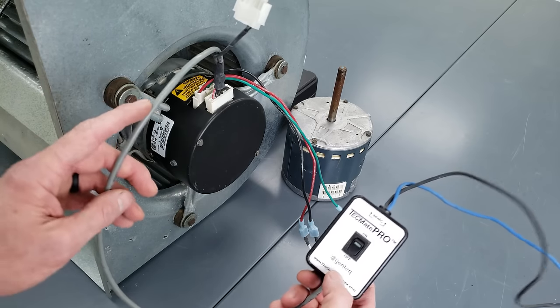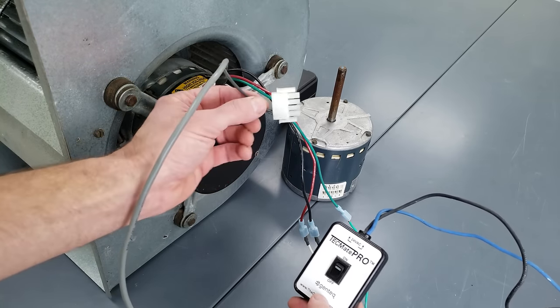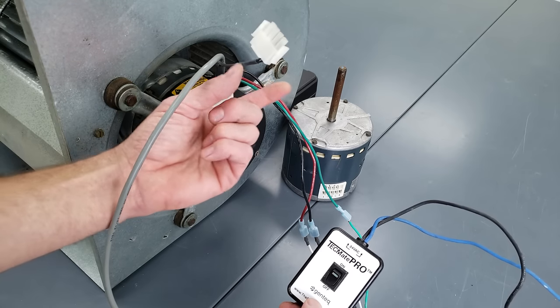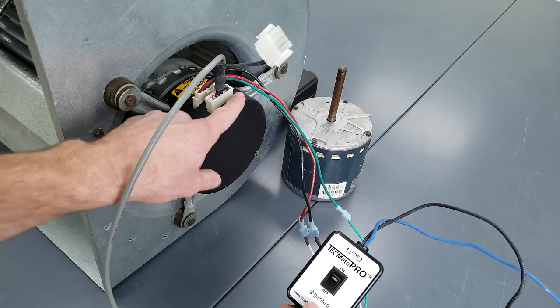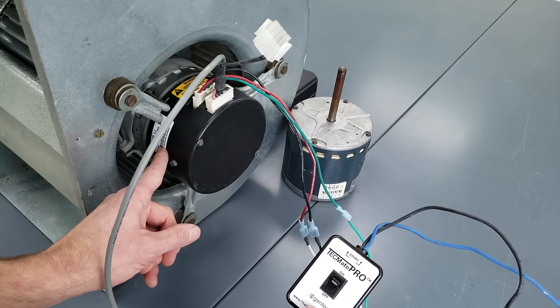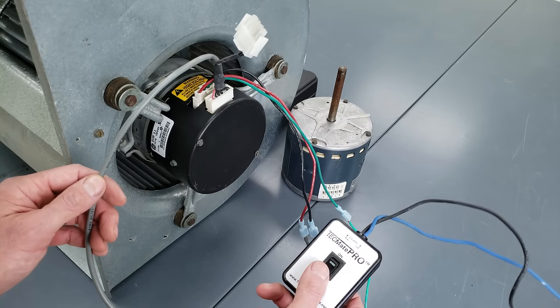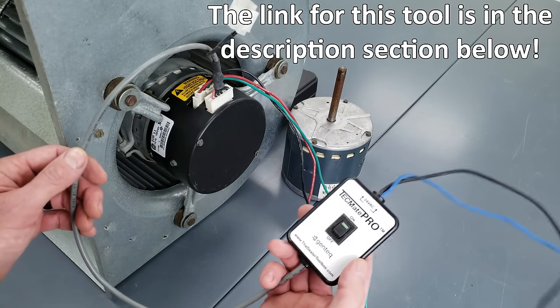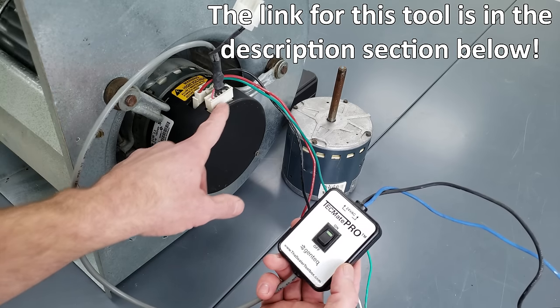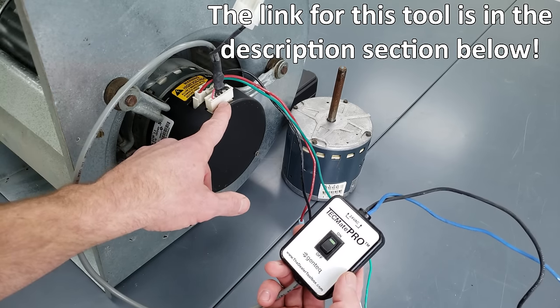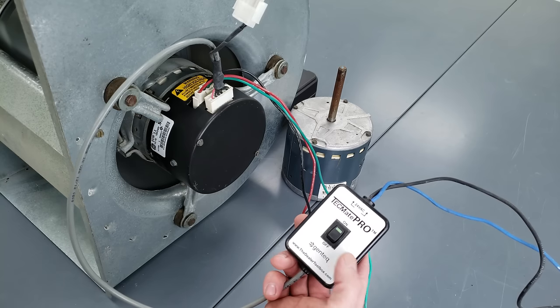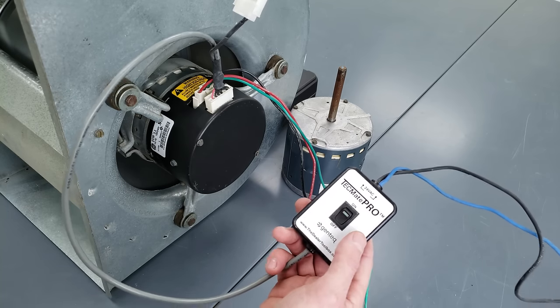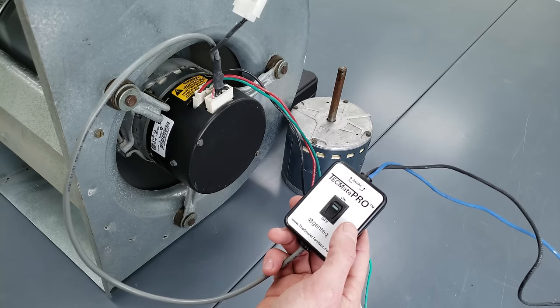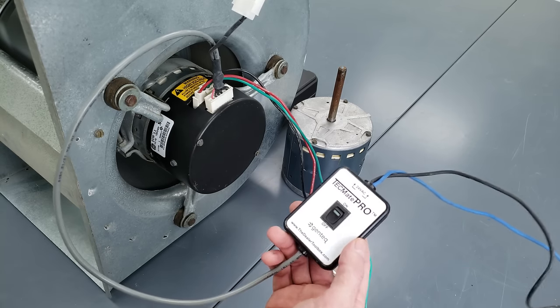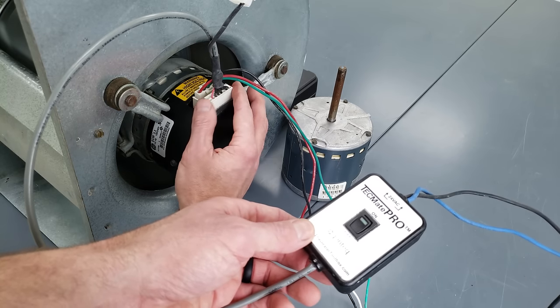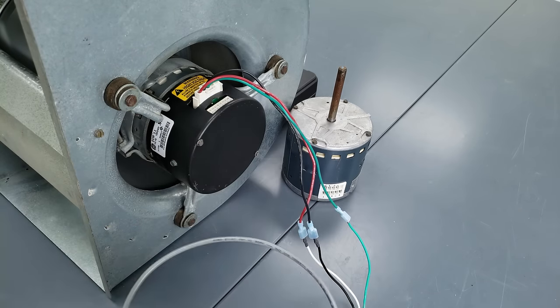This TechMate Pro comes with a 16-pin connector here and a 4-pin connector here, and the 4-pin is for the 3.0 version, and the 16-pin connector is for the 2.3 version. So what I'm going to do is turn this blower motor on by giving it a signal right over here on the 16-pin connector. Now I'm going to tell it to shut off. However, you see that it's not shutting off, and I can even remove the communication wires and it's still not shutting off.